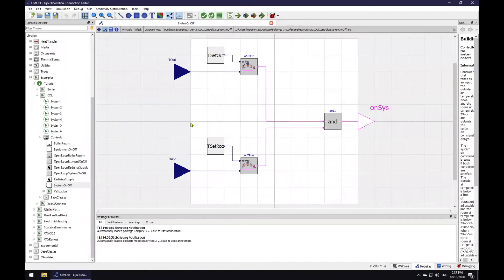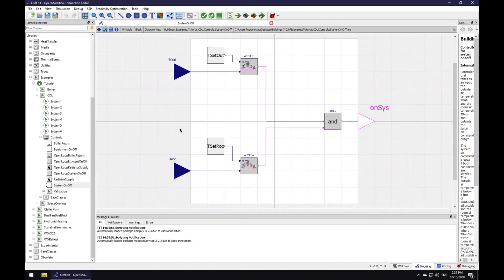This model consists of CDL blocks. CDL is control description language. On the far left, we have two interfaces to receive sensor signals, one from the outdoor air temperature sensor and the other from the room air temperature sensor.